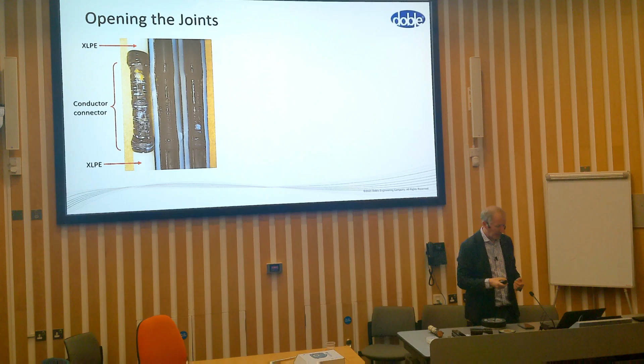There are these strange little brownish-yellow marks, which we didn't actually analyse, but I'm pretty convinced they're down to partial discharge activity. There's also a lot of grease. And going back to those contaminants we could see, there were little bits of wire embedded in this tape layer right next to the fault path.